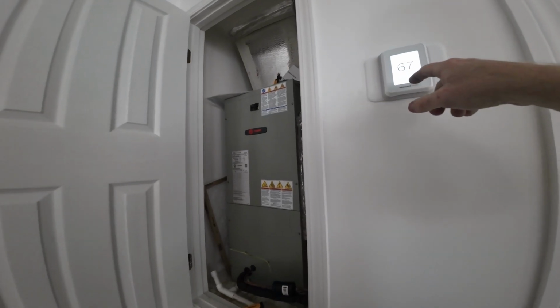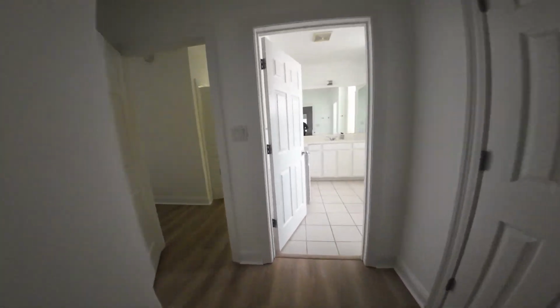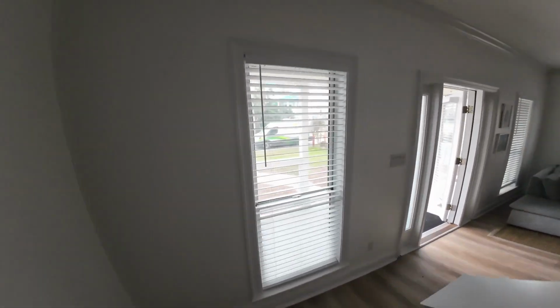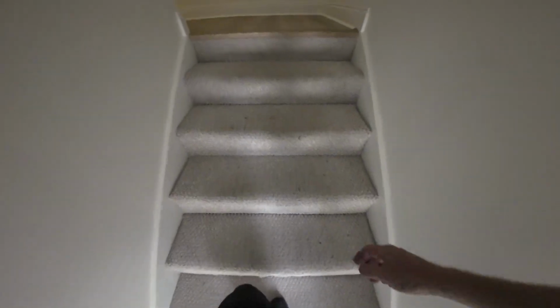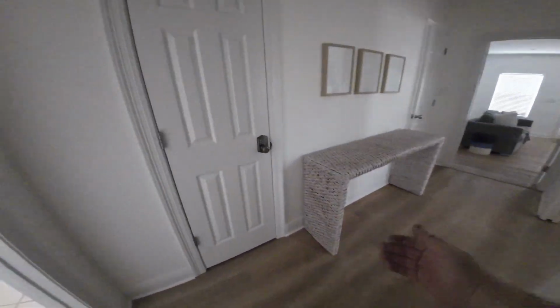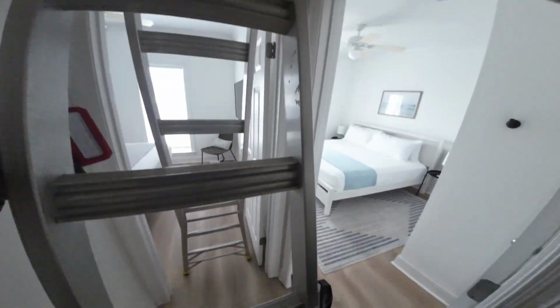The refrigerant stuff looked fine, so I'm gonna do some more airflow tests. I'm gonna go take my stuff off and make sure that it's not oversized or undersized, or what's going on, if I just need to adjust the fan speed. So I got this 1.5 ton system on 441 square feet. So I'm gonna climb in the attic, double check the ductwork, and see what it's actually cooling, instead of guesstimating and assuming this or that.